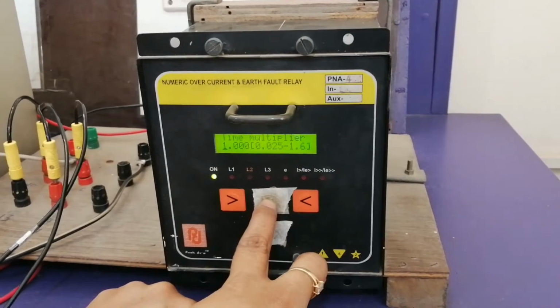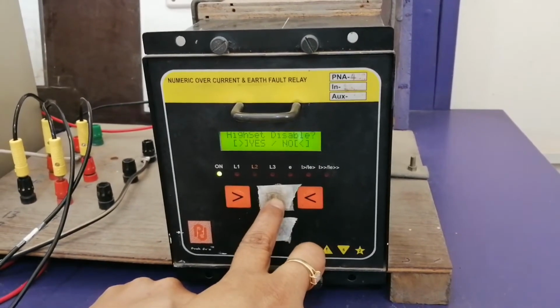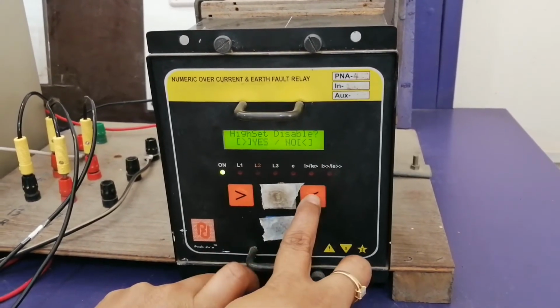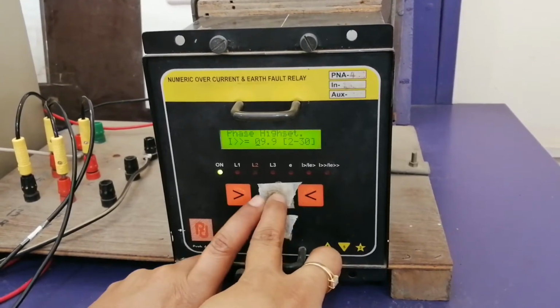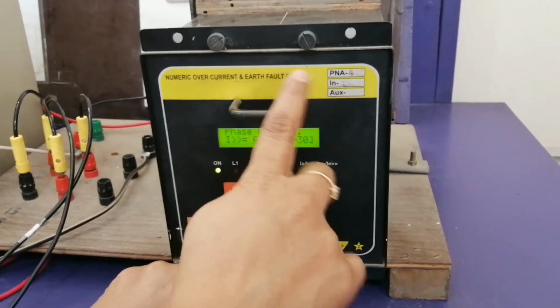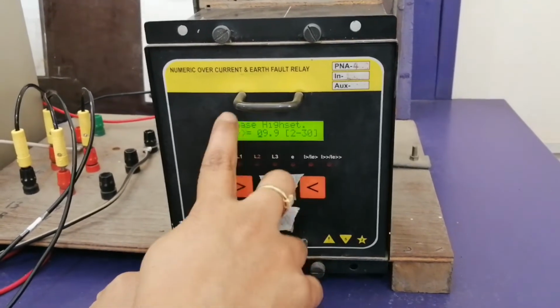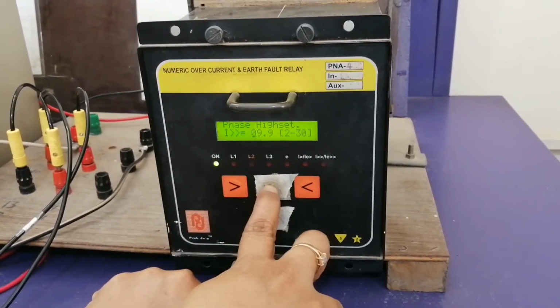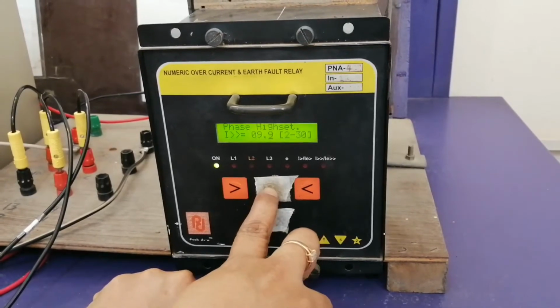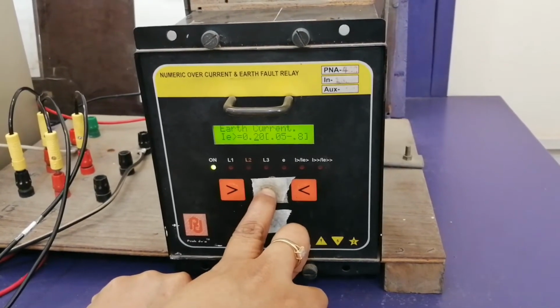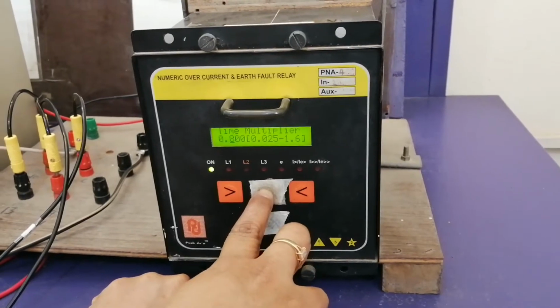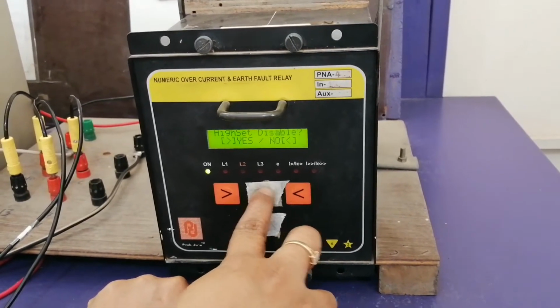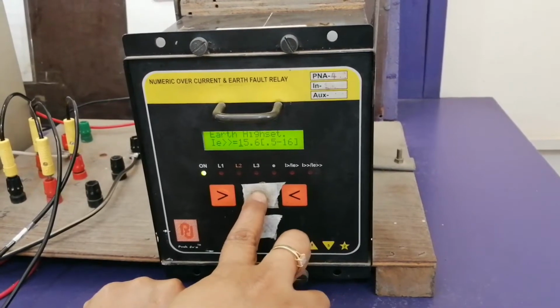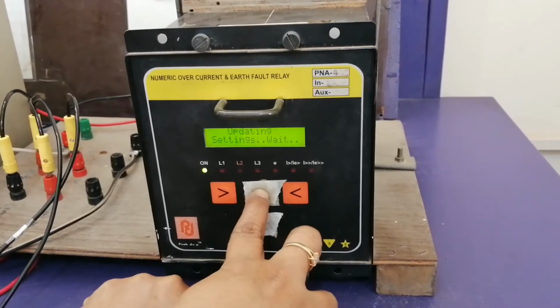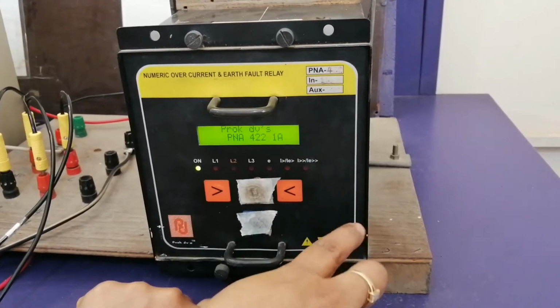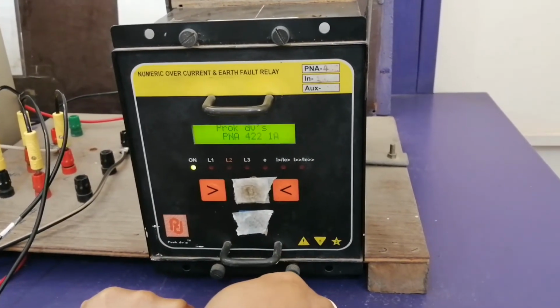My TMS is 1, time setting multiplier is 1. High set disable, I am pressing no. If I enable it, my relay will operate for over as well as earth fault. So I am disabling, no. Now after this, all the readings correspond to your earth fault relay. So just scroll the button, enter. Don't change any values. These all correspond to your earth fault relay, but I am conducting the experiment for overcurrent relay. So go on pressing enter. These are the settings which you have to do for the relay box, earth fault relay box.